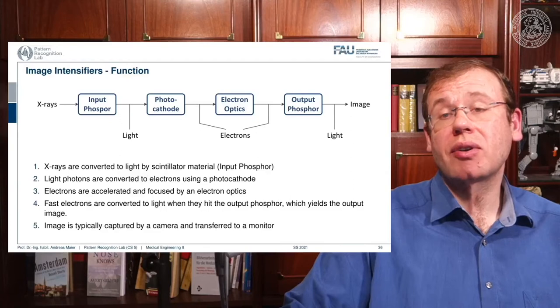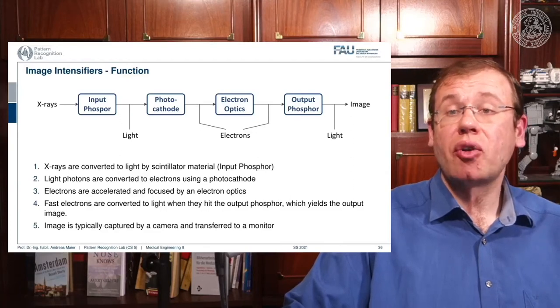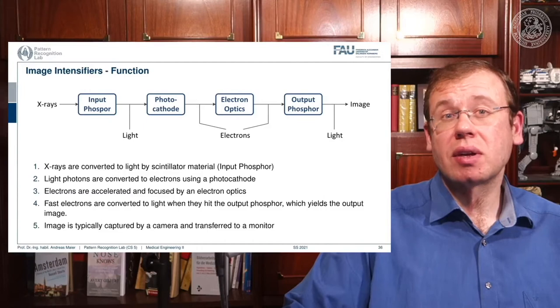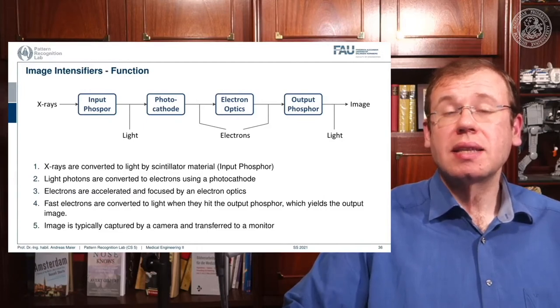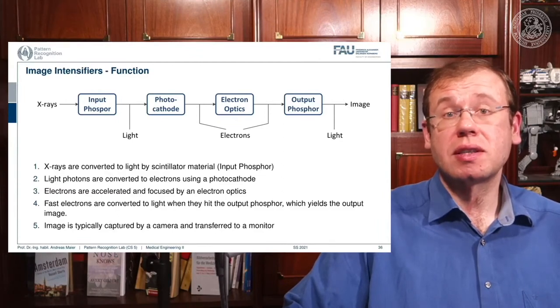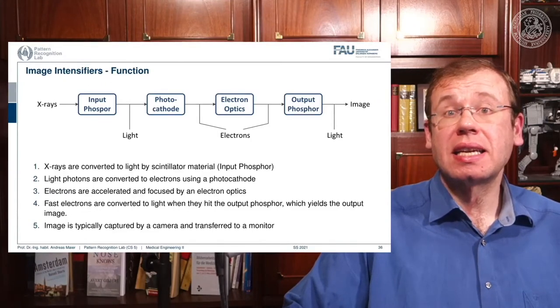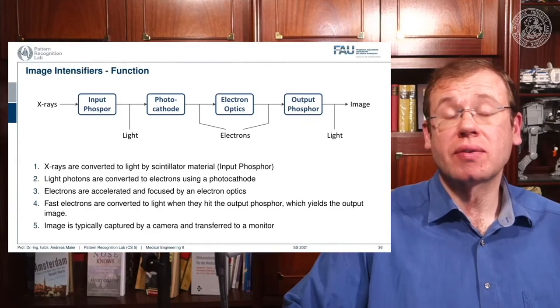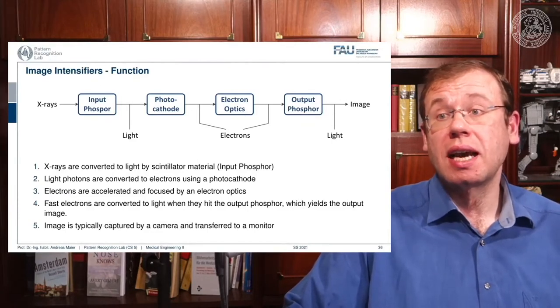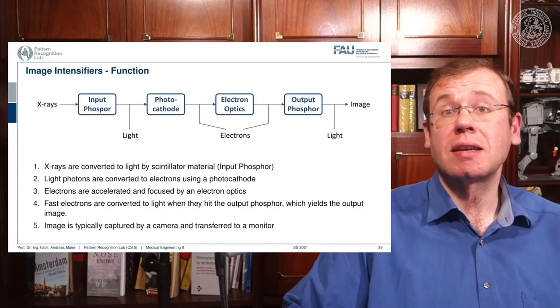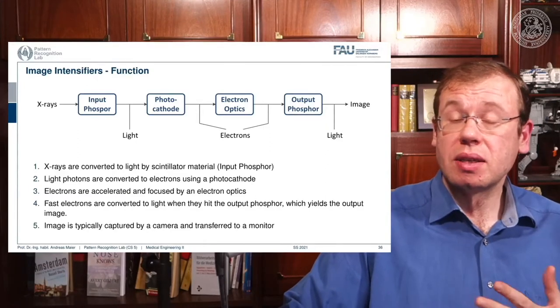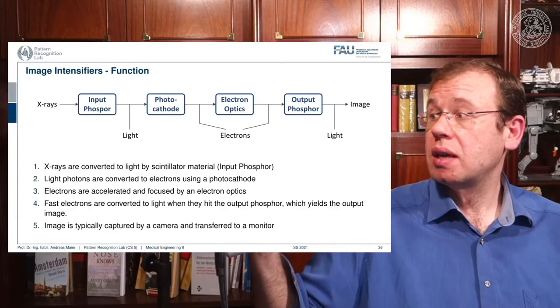Image intensifiers were first introduced in the late 1940s for fluoroscopy applications. Fluoroscopy is generating entire movies of x-rays, so you need very high sensitivity. Image intensifiers made the usable signal for display much more efficient, allowing x-ray dose to be reduced, which then enabled entire x-ray movies. These x-ray movies are still called fluoroscopy. In such an intensifier you generally have a few steps of conversion: first an input phosphor generates visible light from the x-ray.